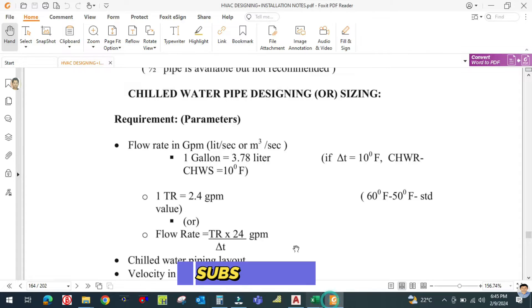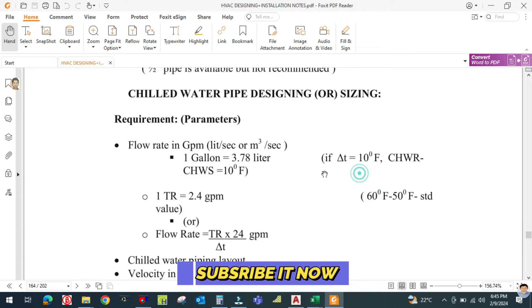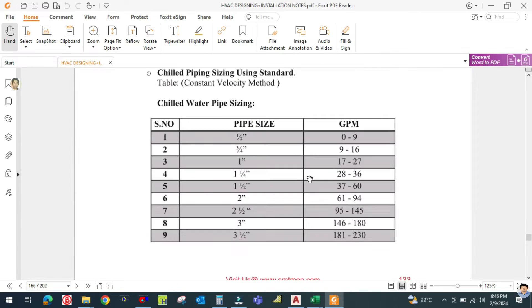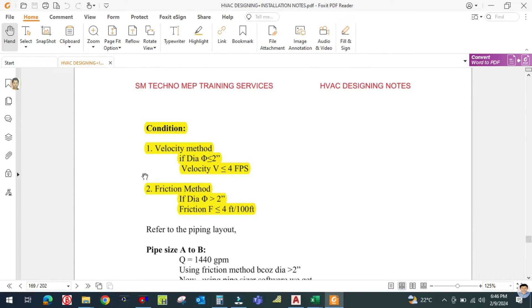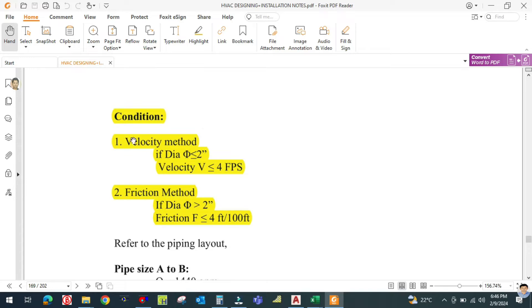Now let me open the condition for pipe sizing. The condition is: if the pipe diameter is less than or equal to 2 inches, the velocity should be less than or equal to 4 feet per second. And if the pipe diameter is greater than 2 inches, the friction loss (head loss) should be less than or equal to 4 feet per 100 feet.